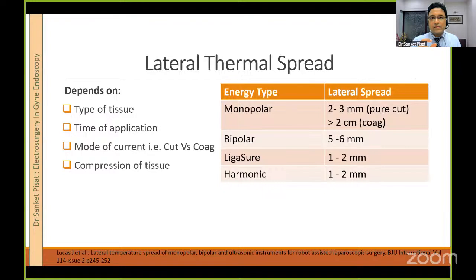This is one of the premises on which LigaSure works, where graded compression is provided between the tissue jaws, and you find that there is minimal lateral spread because the compression is surgeon independent and current will flow minimally between the two jaws. With maximum compression will come minimal lateral spread. So on a head to head comparison, if you look at monopolar in the pure cut mode, there is just 2 to 3 millimeters of lateral spread. So monopolar used properly is not a defective instrument.